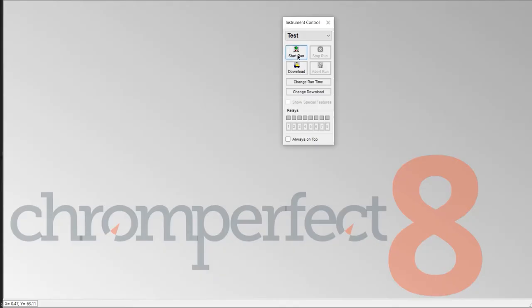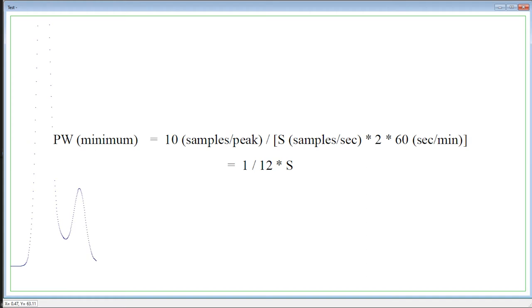The minimum effective peak width is determined by the sample rate. Assuming that the peak width at half height is one-half the baseline width, to have at least 10 data points across the full baseline width of the peak, the peak width at half height must be at least 5 sample intervals. Since the sampling rate s is given in samples per second and the peak width is given in minutes, the following formula gives the minimum peak width for any sampling rate: peak width minimum equals 10 samples divided by peak divided by s samples per second multiplied by 2 multiplied by 60 seconds per minute equals 1 divided by 12 multiplied by s.